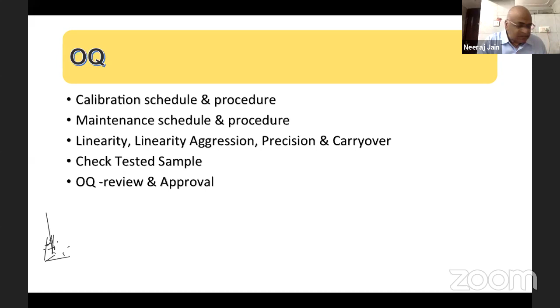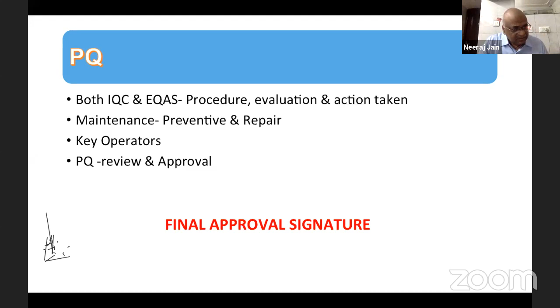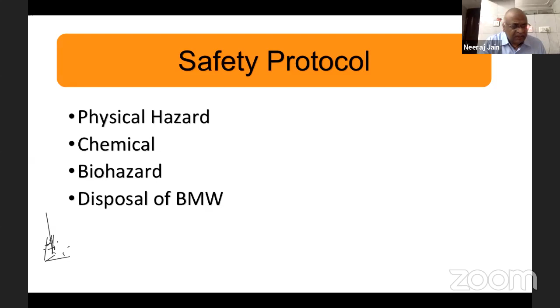Regularly run, and regularly participate in, internal quality control and EQAS. You shall have a well-documented procedure. Whenever you get any outlier, evaluate, do the root cause analysis, take appropriate action, document it, and monitor your action for its effectiveness. Then any maintenance, preventive or repair, shall be documented. Who are the key operators of your machine for a particular period? Their names should be available close to the machine so that you know only trained and authorized persons are operating your machine. Then somebody is approving, okay, we are maintaining all these things, and this is your IQ, OQ, and PQ. Also develop a safety protocol in your laboratory: physical hazard, chemical hazard, biohazard, and disposal of biomedical waste as per your biomedical waste guidelines.